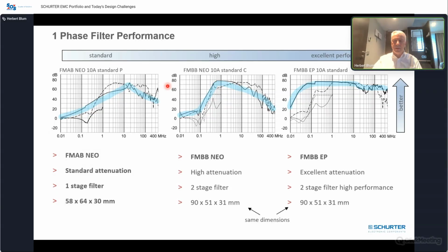And if this is not good enough, I probably will use a triple stage filter, or what we think is more efficient, a high performance dual stage filter, as you can see here, which provides a much better attenuation, especially at the lower frequency range. In the middle, it's also about 80 dB. It's not a 100 dB filter, but usually this is not required unless you're talking about special applications like military or test lab applications. There you need 100 dB, or if you have, let's say, several motor drives, it might also be required, but then I would strongly recommend going closer to the noise source and doing filtering there instead of having just one big filter. It's just not cost efficient.